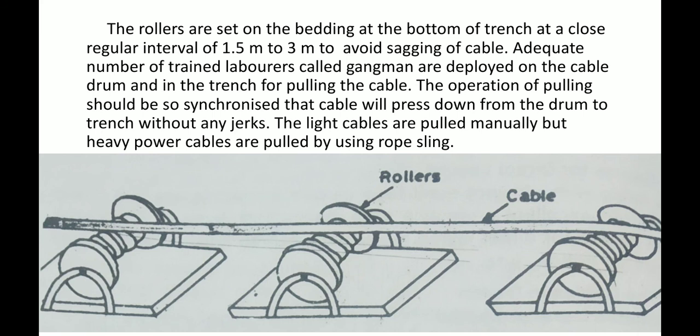The rollers are set on the bedding at the bottom of the trench at close regular intervals of 1.5 m to 3 m to avoid sagging of the cable.